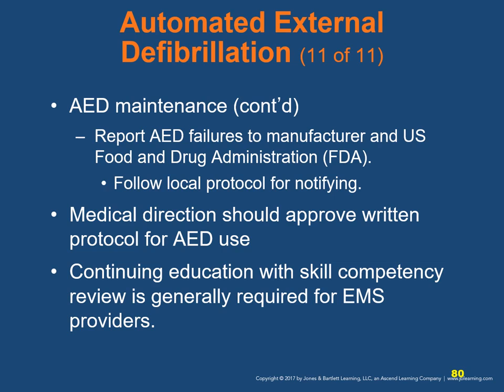And let me clarify something. Back here, previously when I said that shocks should be delivered within 1 minute of the call, that means the timing on the mechanism, from the point where it recommends a shock, and you call it, to the time the machine is ready to provide the shock, should be 1 minute or less. So if your machine is operating outside of that guideline, then that's what they're stating specifically there.